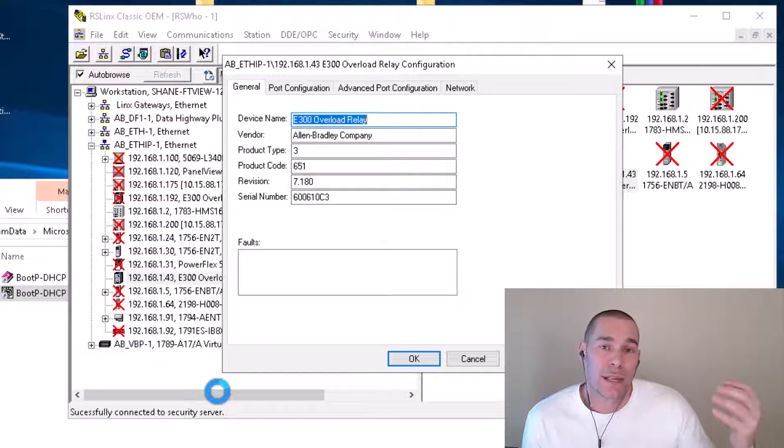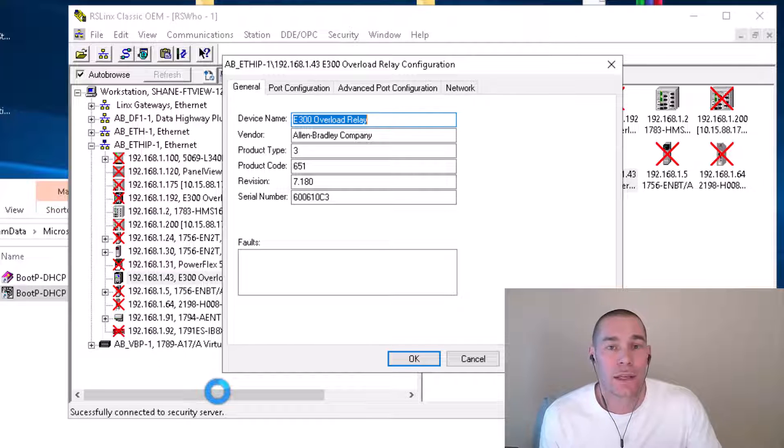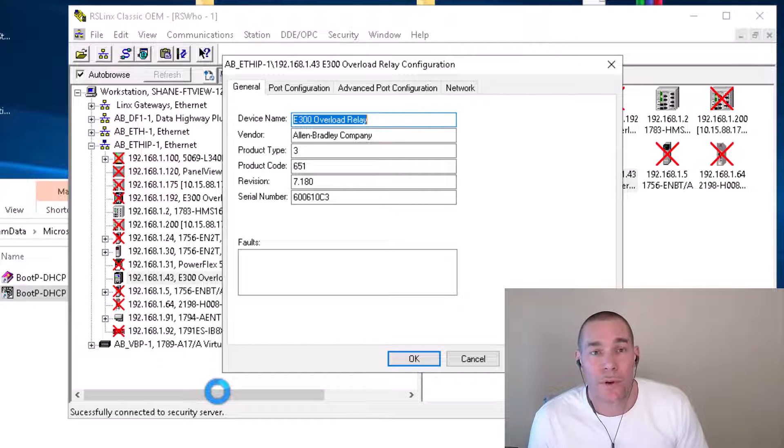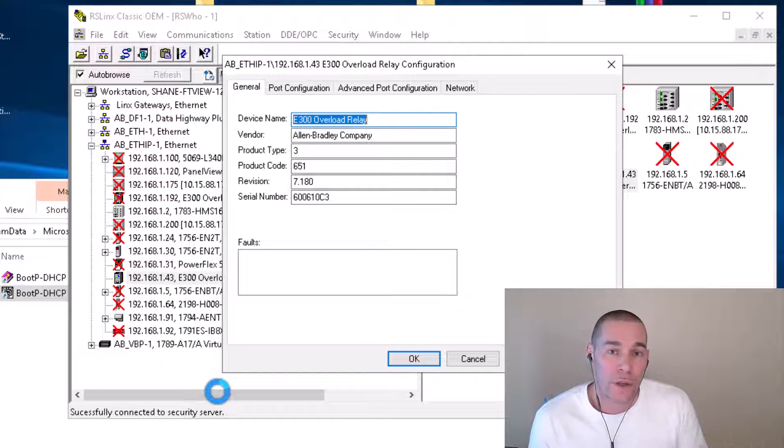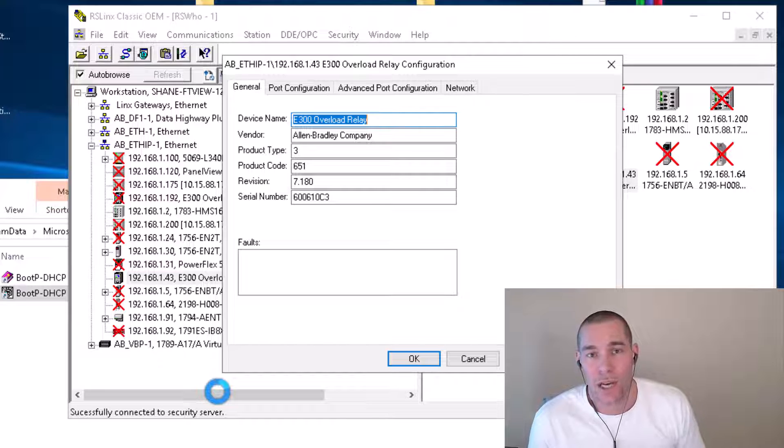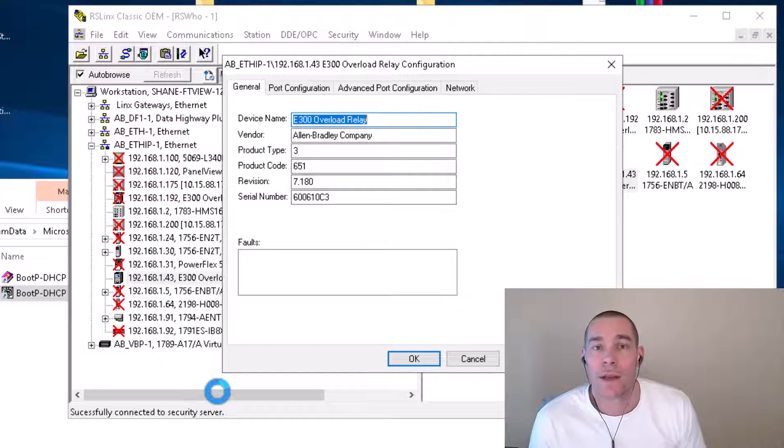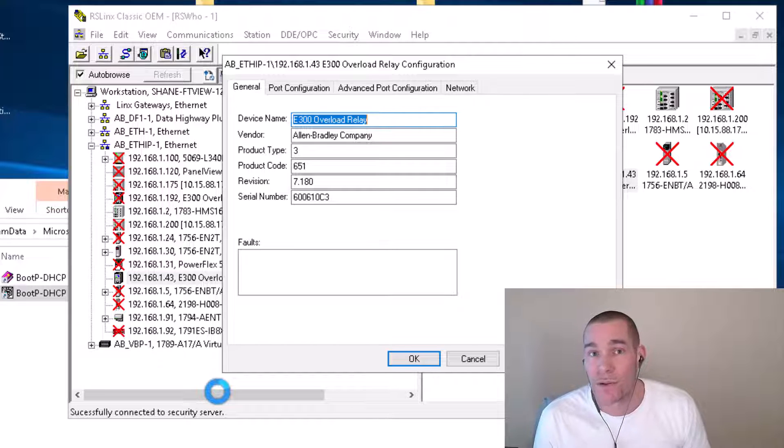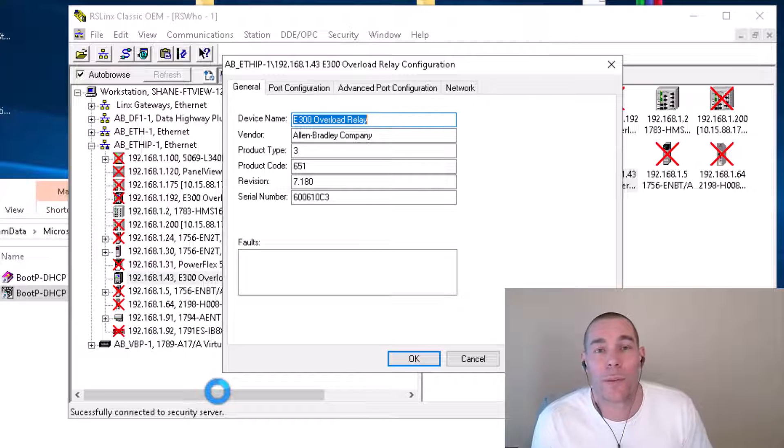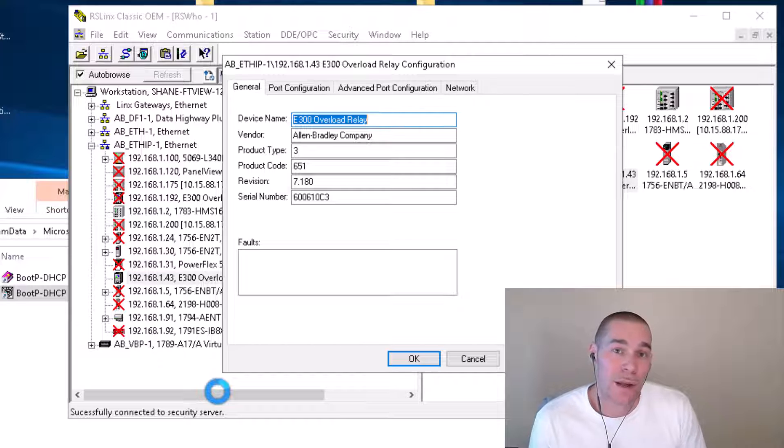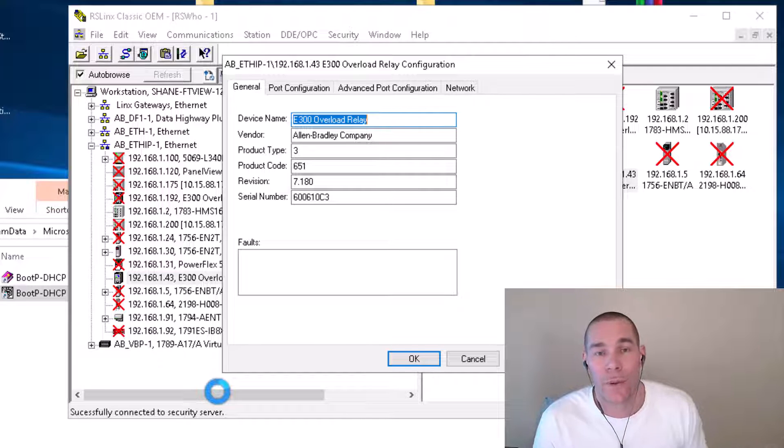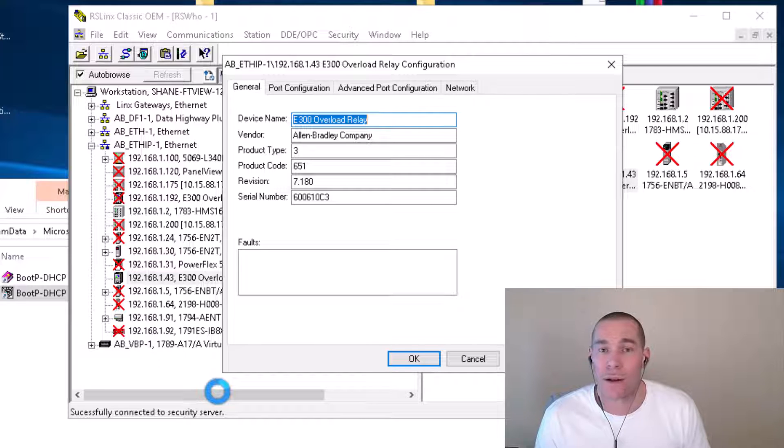You can use this process if you have one running and it goes out, then you can actually go on the webpage after you set the IP address up and restore it and literally be back up and running in minutes. Like I said, it's always the best practice to back everything up or you can go in there and use the webpage to change the parameters if you need to. Again, not everybody uses Studio 5000, but they do use the E300 and not everybody wants to go into Studio 5000 and change their actual parameters from that point as well. Again, if you do make a change in Studio 5000 parameters, then make sure you do the due diligence and backing it up through the webpage anyway so that you do have that JSON file to backup and restore when you need to.